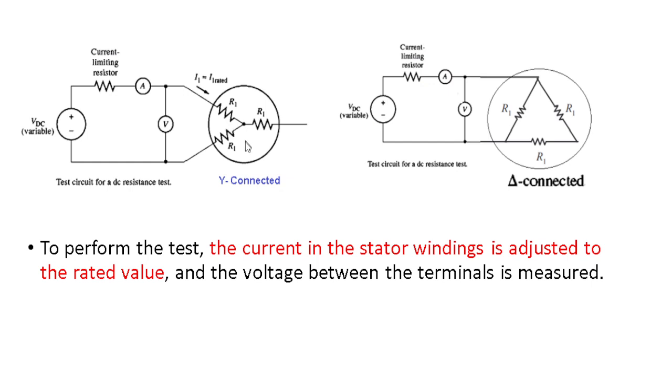To find R1, the stator winding may be Y-connected or delta-connected. To perform the test, the current in the stator winding is adjusted to the rated value using a variable DC source and variable resistor.